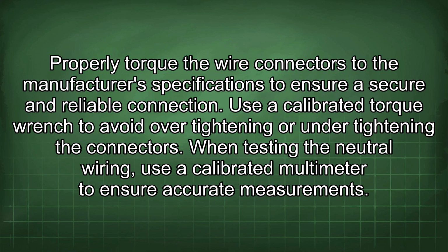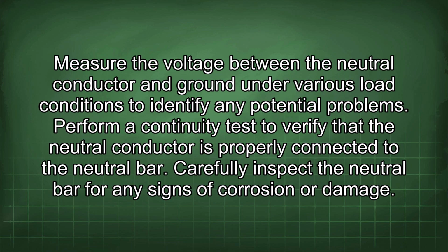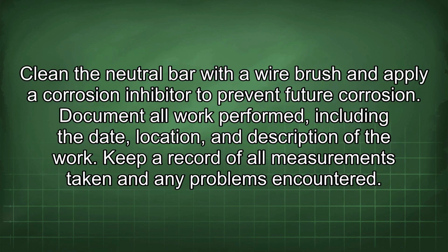When testing the neutral wiring, use a calibrated multimeter to ensure accurate measurements. Measure the voltage between the neutral conductor and ground under various load conditions to identify any potential problems. Perform a continuity test to verify that the neutral conductor is properly connected to the neutral bar. Carefully inspect the neutral bar for any signs of corrosion or damage. Clean the neutral bar with a wire brush and apply a corrosion inhibitor to prevent future corrosion.